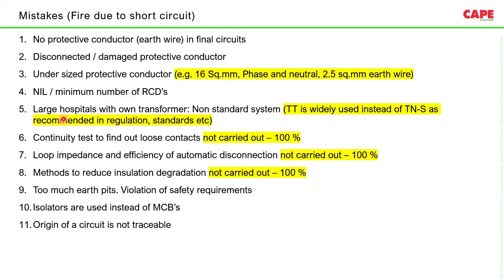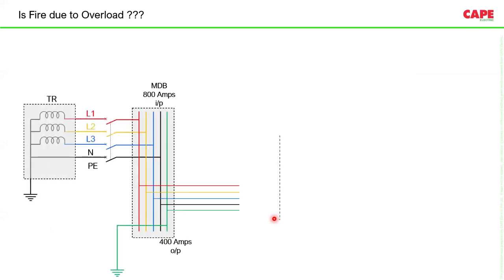The RCDs are not there. A large hospital with its own transformer has non-standard system earthing. TT is widely used instead of TN-S as recommended in the regulation standards. Continuity tests to find loose contacts are not carried out, unfortunately 100%. Fault loop impedance is not measured, 100%. Methods to reduce insulation degradation are not carried out. Too many earth pits, a violation of safety requirements. Isolators are used instead of MCBs. The origin of a circuit is not traceable. These are some of the issues which we find.